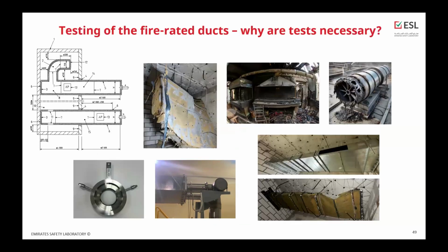device. Why do we need to test the ducts? To confirm that this duct design is okay to call it a fire-rated duct, because inappropriate suspension devices may result in collapsing of the duct inside the furnace, or the wrong design of the duct may result in collapsing of the cross section, which makes the duct no longer fulfill the intended function, and the duct cannot extract the smoke from the furnace.